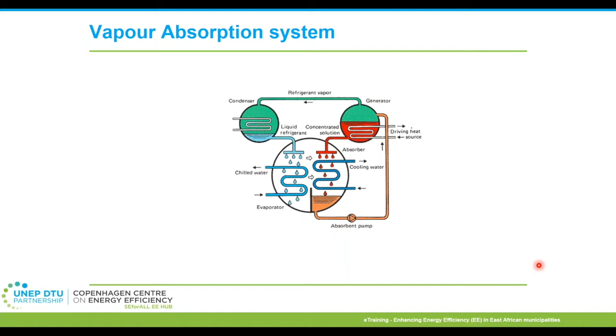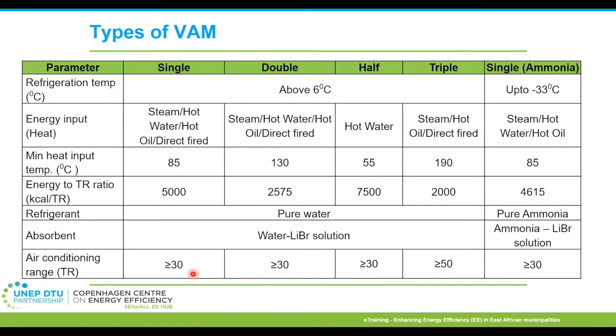This table shows different types of vapor absorption machines available. The key takeaway is the ability to choose the system based on the heat source and heat quality you have. For example, if your building or industry has a minimum of 85 degrees centigrade hot water available that's simply being rejected into the drain, and if it's of significant quantity, you can utilize that heat content by passing it through a VAM machine - a vapor absorption machine - and easily get about 30 TR equivalent of cooling load capacity chiller in place.